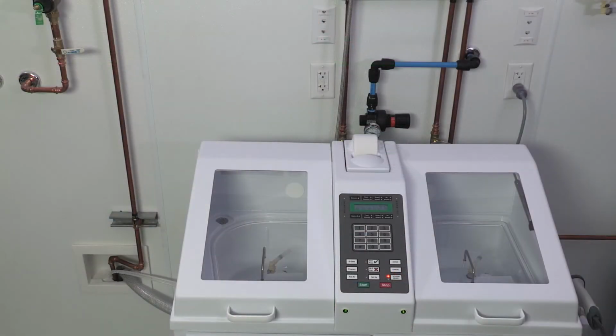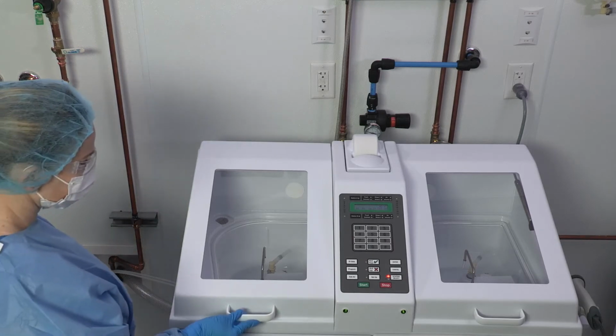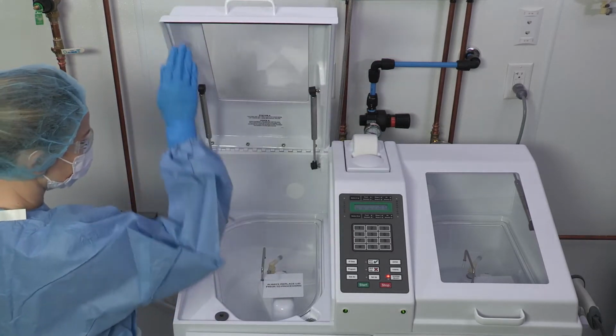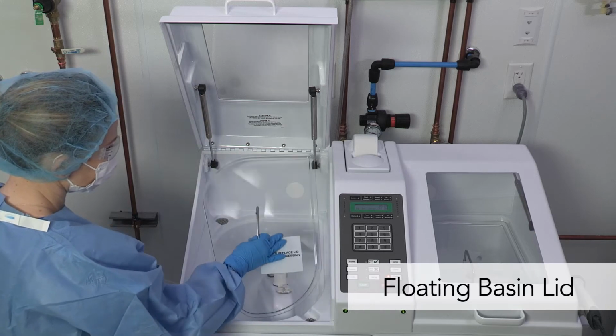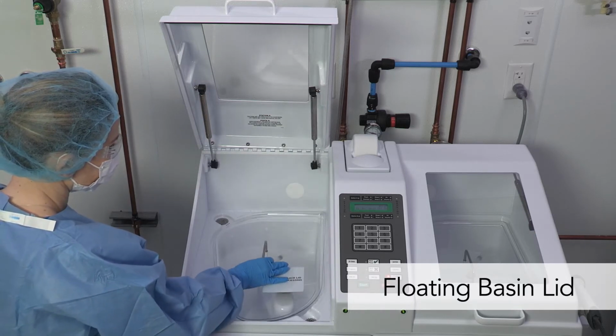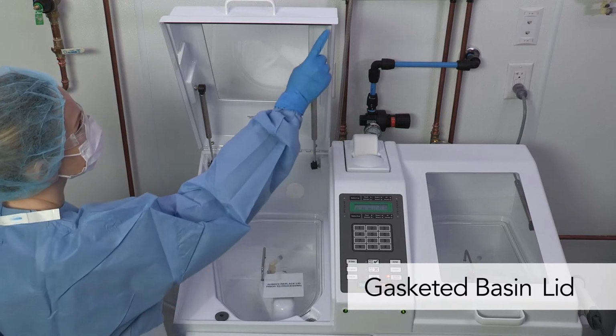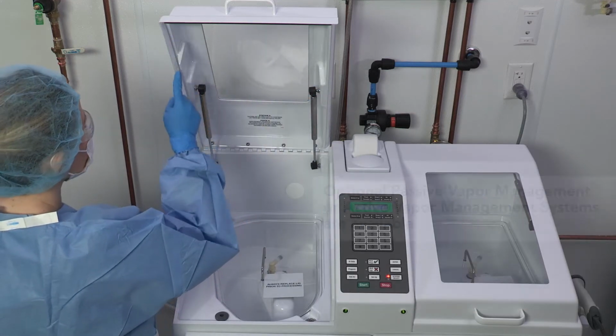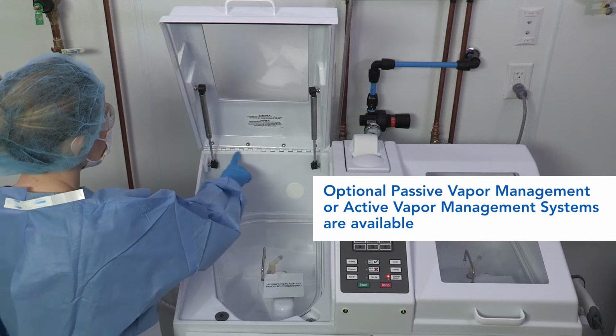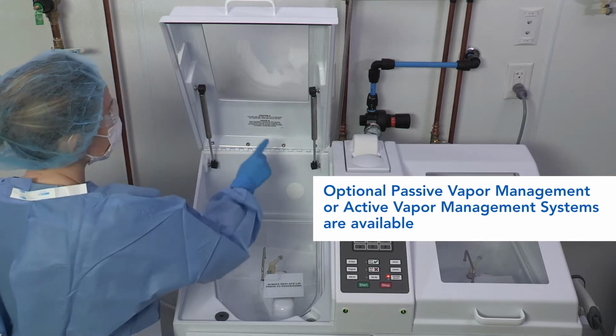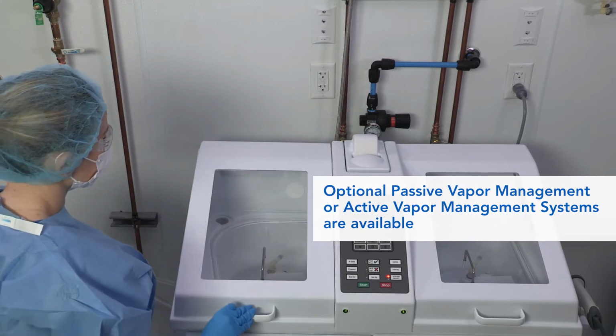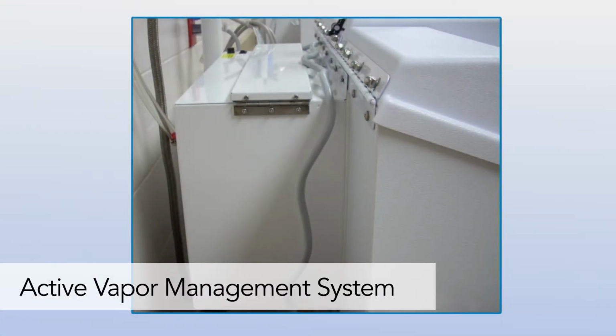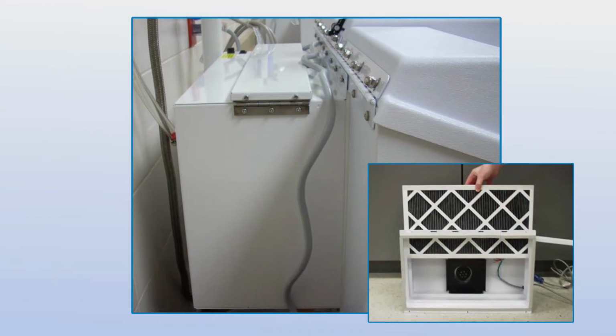The DSD EDGE Reprocessor minimizes vapor and fume exposure as compared to manual reprocessing. A floating basin lid minimizes and restricts chemical vapors, while a gasketed basin lid suppresses vapors. Optional passive vapor management or active vapor management systems are also available and designed to minimize staff exposure to chemical fumes. The active vapor management's exhaust fan and carbon filter removes fumes from high-level disinfectant during the disinfection cycle.